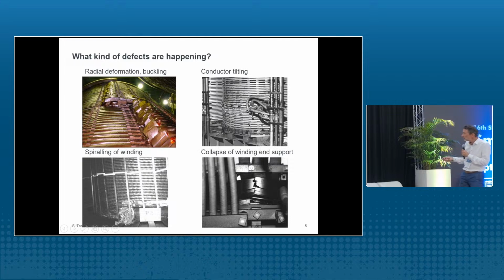Or conductor tilting. Yeah, here conductors, due to the compressional force, are tilted. We have also collapse of winding end support. Yes, so at the end of the winding you have thick wooden plates to press the winding, and in this case this wooden plate is broken. Spiraling is the winding itself is turned. This is all done due to excessive currents in the winding.